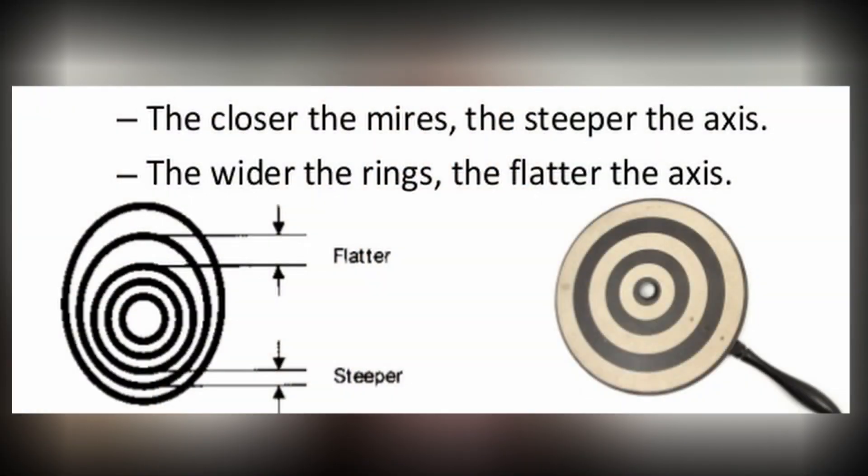In Placido disc interpretation, the appearance of the mires is what the software interprets to determine the shape of the cornea. Areas where the mires are closer together correspond to a steeper corneal curvature, and the further apart the mires are, the flatter the corneal curvature. A perfectly spherical eyeball would demonstrate equally spaced mires over its entire surface. However, most people have variations where we would note distortion or wavy mires. Most software now incorporates a color scale which really helps us visualize the cornea. The Placido disc technology also gives us an idea of how healthy a person's tear film is in the context of dry eye disease.